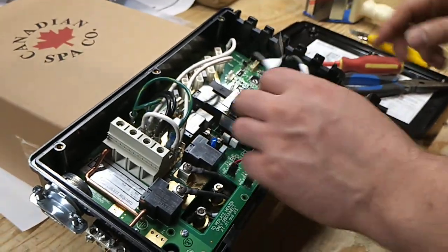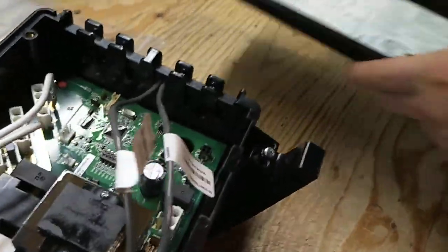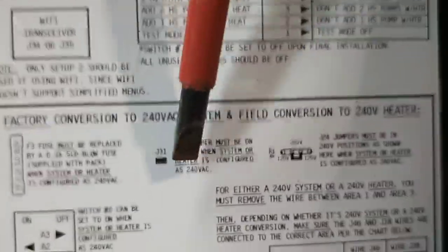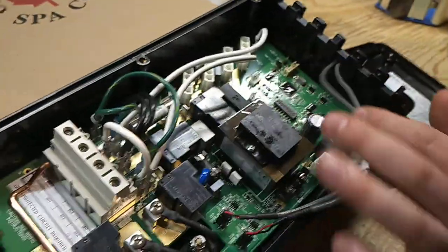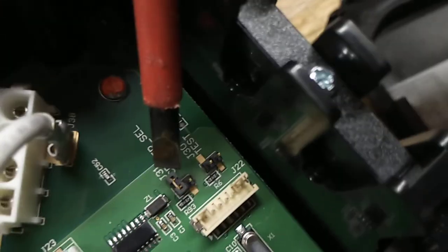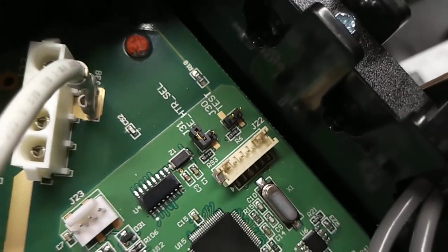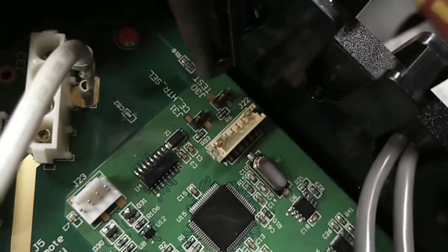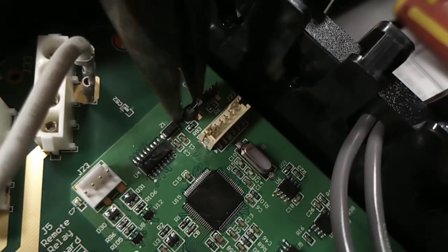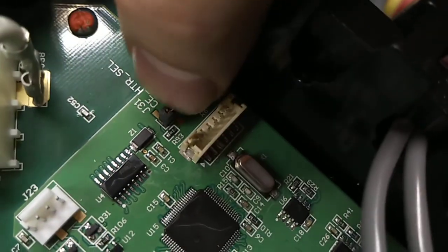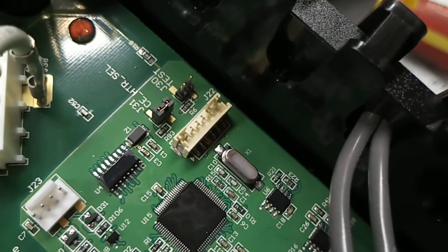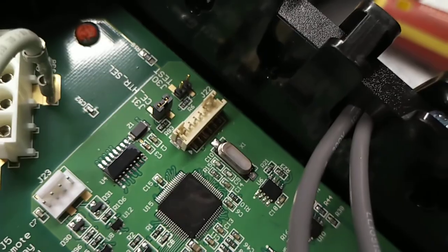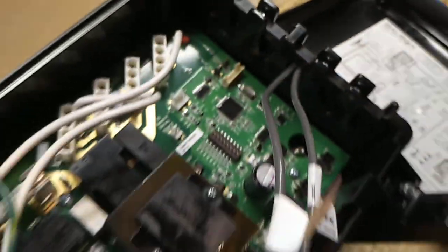Number three, we're going to be looking over on the right-hand side. We're going to look for the J31 jumper pin. This J31 jumper pin, another very small pin, this is a little black one here. It's located right here on the right-hand side. As you see, this one's located, it's only across one of the pins and it's located vertically. We're going to want to take this off and put it across, jump across both pins. Make sure that's pushed down and secure. So that's the J31. You want to jump both pins there instead of just the one, which is used for 120 volts.